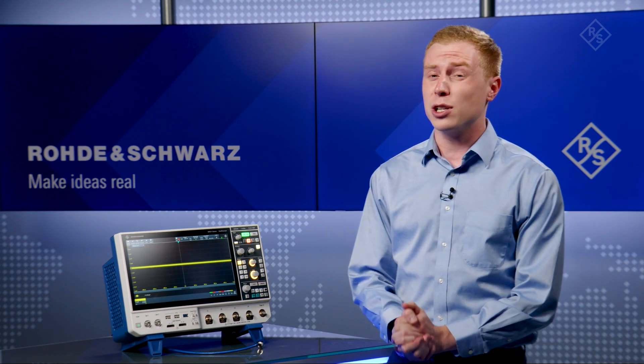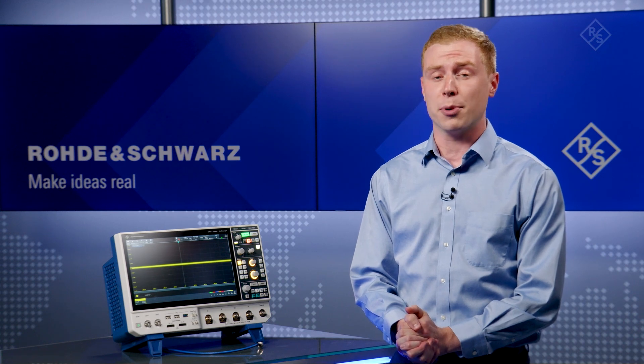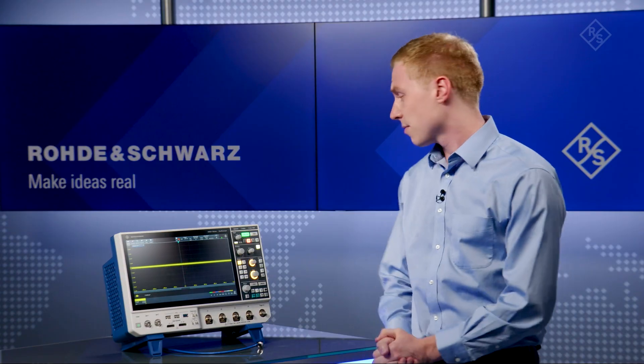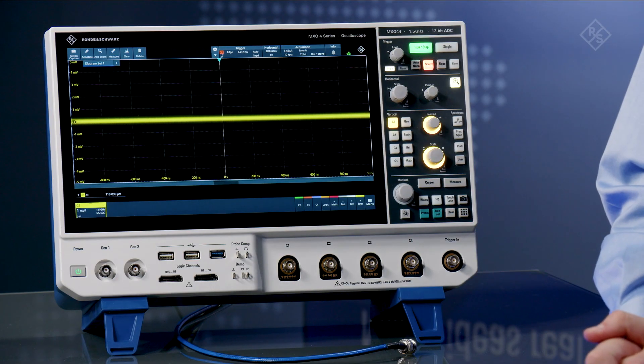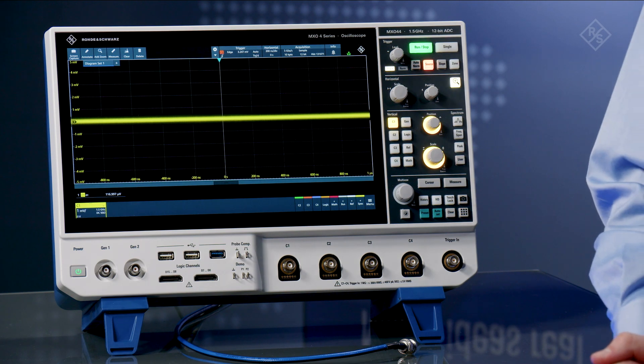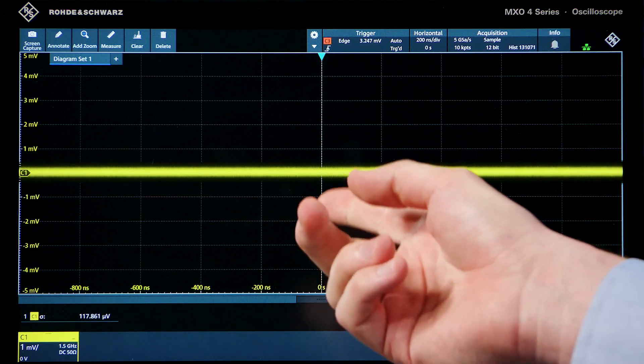A quick way to characterize instrument noise is to disconnect all inputs and measure the thickness of the signal. Let's take a look. Users often care about noise at the most sensitive vertical settings, and the MXO4 scope has the lowest noise floor in its class, at 1 millivolt per division.